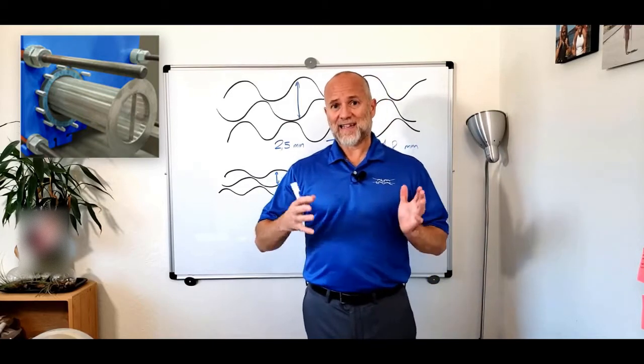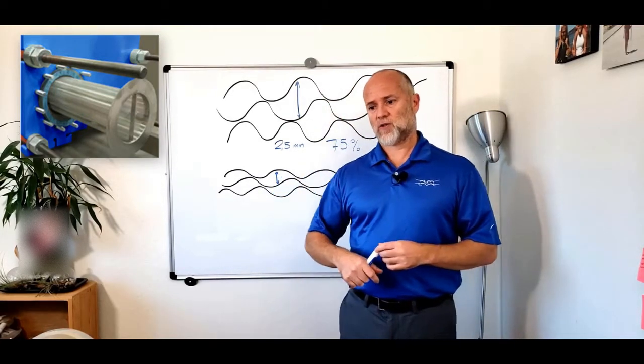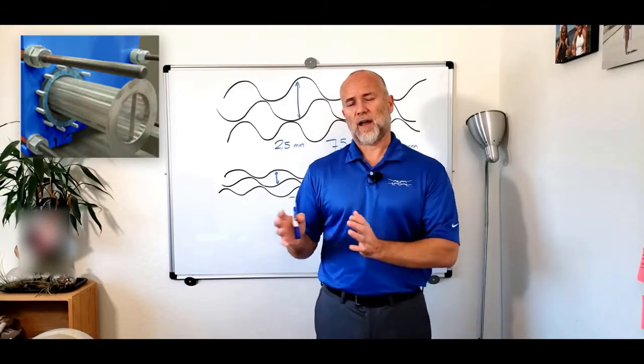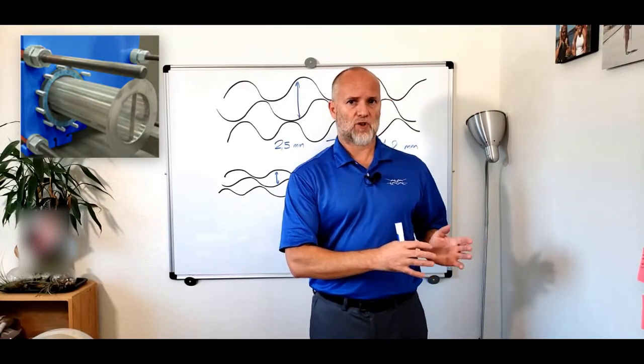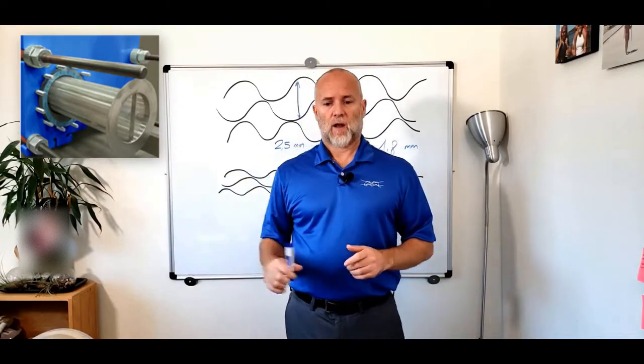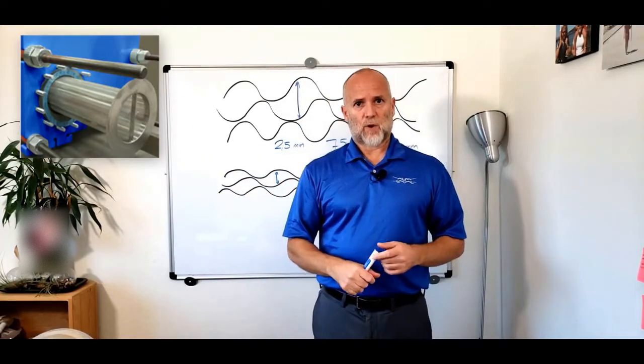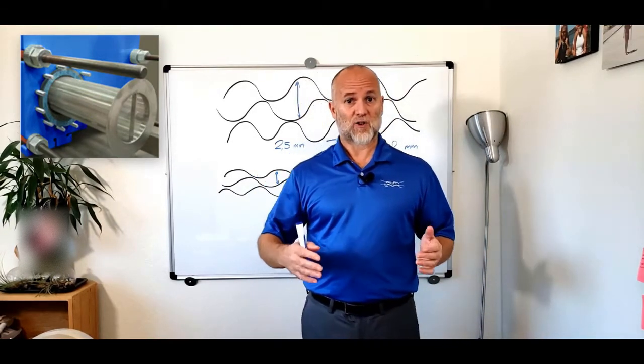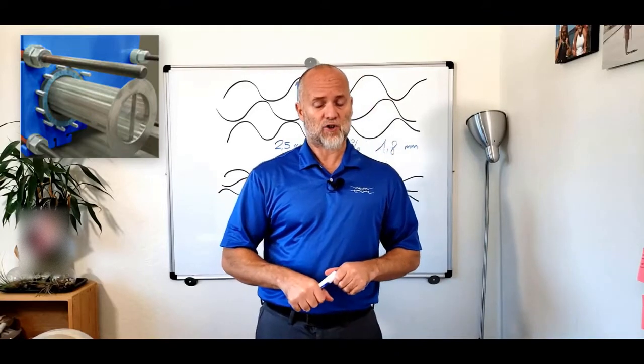And it has another advantage in that it's inside of the heat exchanger, because another concept that is important is that you position your strainer as close as possible to the heat exchanger so you don't have any contaminants after the strainer. In this case with the port filter, and here you can see a picture of a port filter, you see that the port filter actually is kind of embedded inside of the heat exchanger.